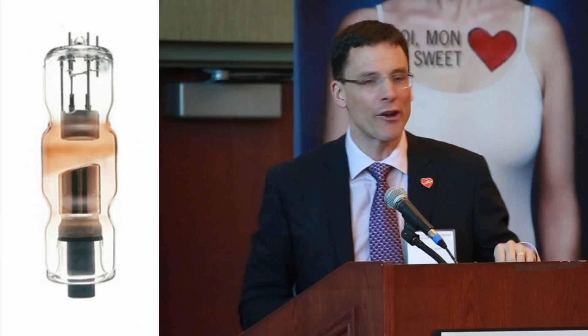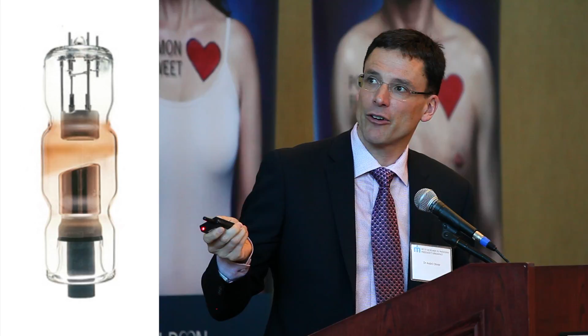So now if we flash forward, this is pretty much a modern X-ray tube, but the concept is the same from what was originally created. We have a current that's passed through here to a filament. We don't see the filament very well. The current causes the filament to generate electrons. There's a voltage across the tube, so the electrons come across and hit a little tungsten plate that's on the other side. The electrons interact with the tungsten and generate these X-rays that then exit the tube.